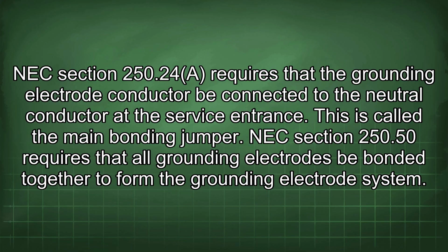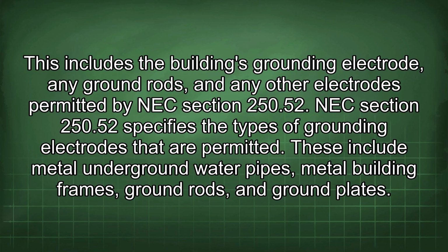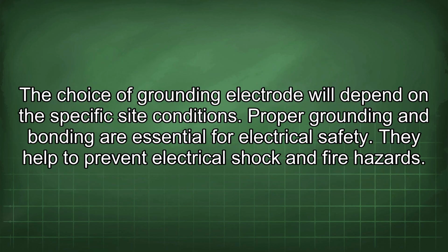NEC section 250.50 requires that all grounding electrodes be bonded together to form the grounding electrode system. This includes the building's grounding electrode, any ground rods, and any other electrodes permitted by NEC section 250.52. NEC section 250.52 specifies the types of grounding electrodes that are permitted. These include metal underground water pipes, metal building frames, ground rods, and ground plates. The choice of grounding electrode will depend on the specific site conditions.